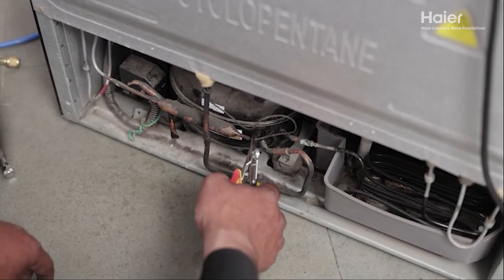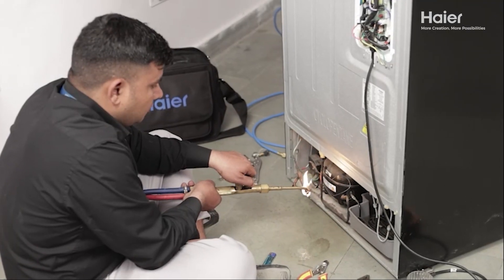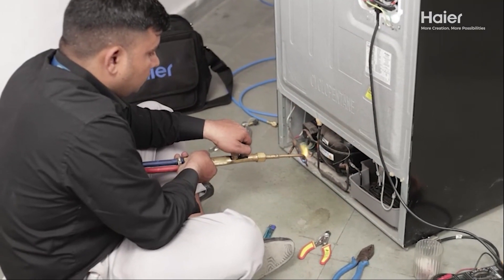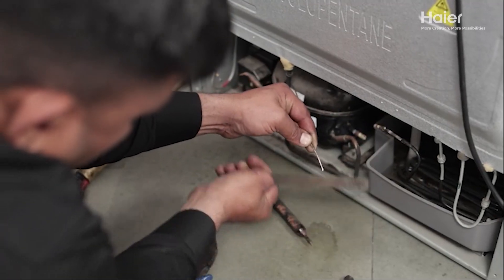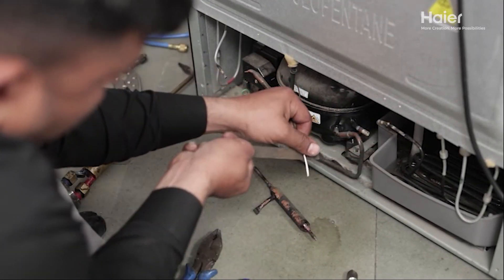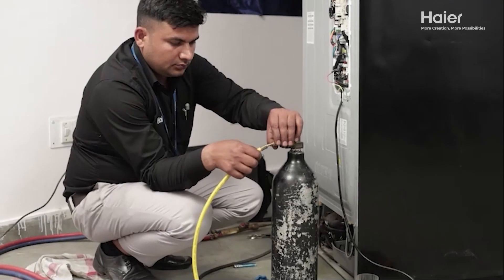Carefully cut the capillary tube from the dryer with a cutter for removal. Now, debraze the dryer from the condenser and the condenser from the compressor port. Clean and file the capillary and condenser ports, then remove by nitrogen any burrs and carbon particles that could affect the new installation.